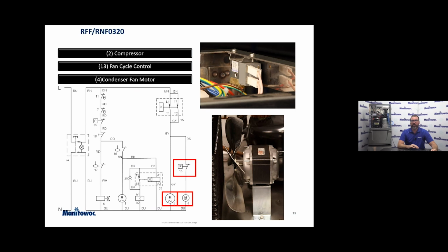And again, we do have a fan cycle control on this system. Now, remember that that's wired in parallel, so the system may still start up, may function properly initially, but if you're having an issue where we have low production or it's cutting out on high pressure, something of that nature, we're going to want to look at that fan cycle switch and make sure that it's opening and closing as need be based on the pressures that are spec'd by the particular machine. But remember, this machine will start whether or not that fan cycle control is working properly. So a faulty fan cycle control will not be the reason for a no start condition on a Flaker Nugget.